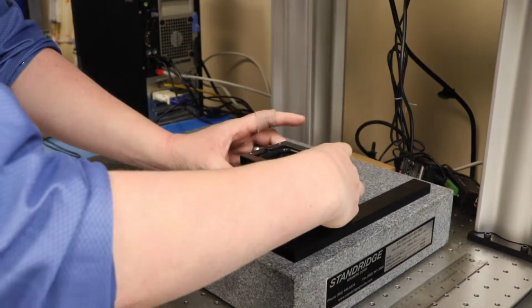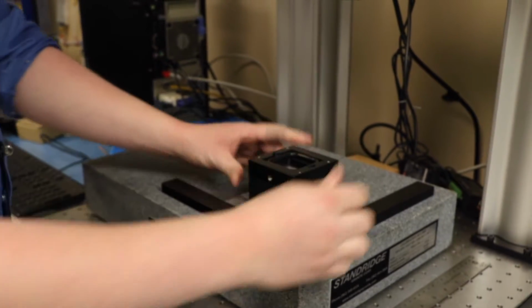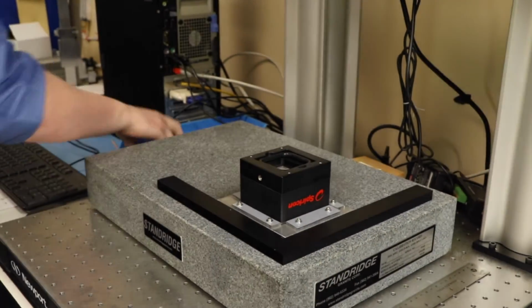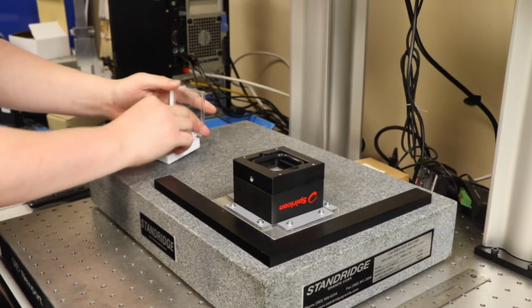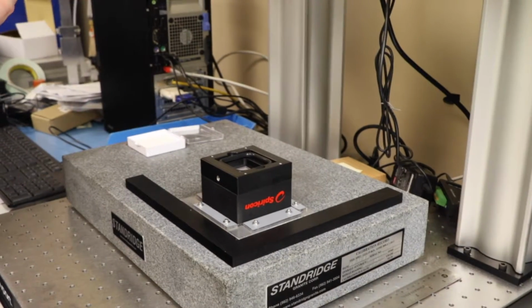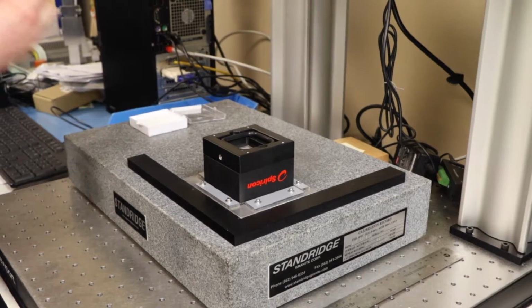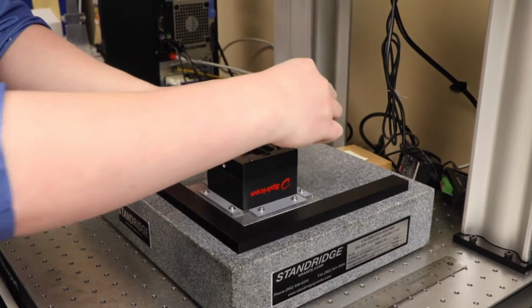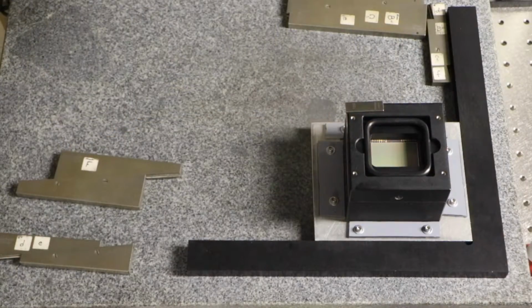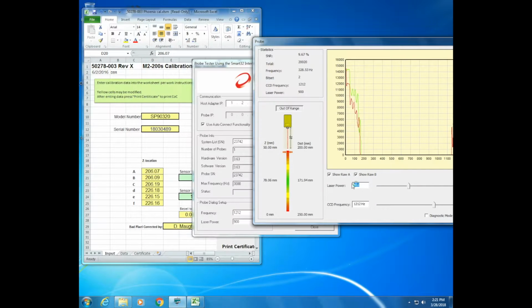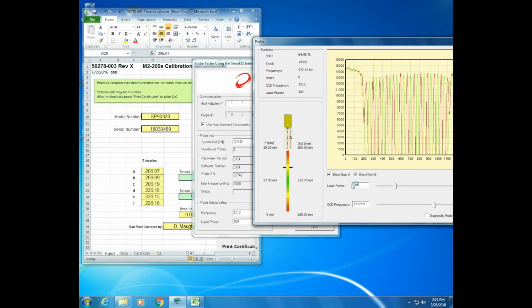place the camera face up into the jig. This is a 1/100th gauge block. It's more reflective than the camera, that's why we're using it. Laser power for here is generally around 500, but it needs to create a more U-ish shape in this green and red lined area, so we need to go a little less.